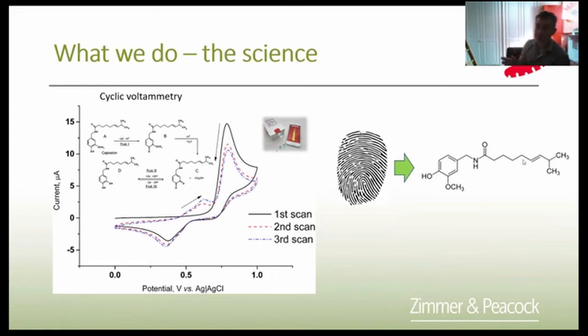And it's really important to realize that we don't then display this raw data to you. We actually interpret the data and give you the Scoville heat unit. So we have a calibration within the instrument that looks at this peak height. It checks that the profile is correct, and then it will report the Scoville heat unit to you. So Richard Compton at the University of Oxford was the inventor. If you ever read his first scientific paper on this, you'll see him use a technique called cyclic voltammetry. Capsaicin is electrochemically active, and it gives very distinctive peaks in the cyclic voltammetry, and those can be used to identify that the sample really is capsaicin.